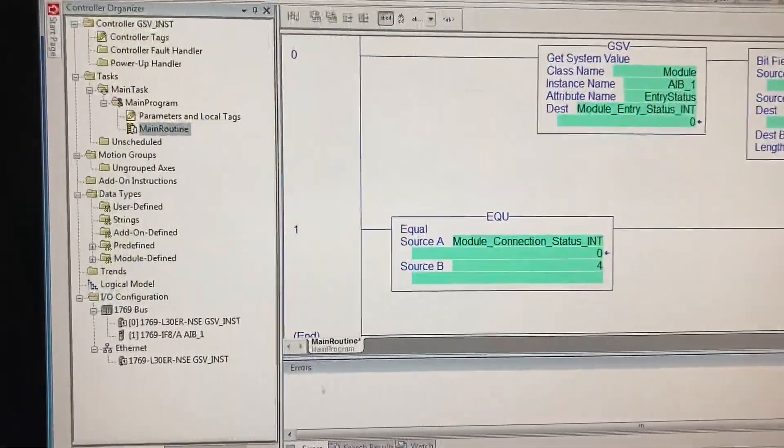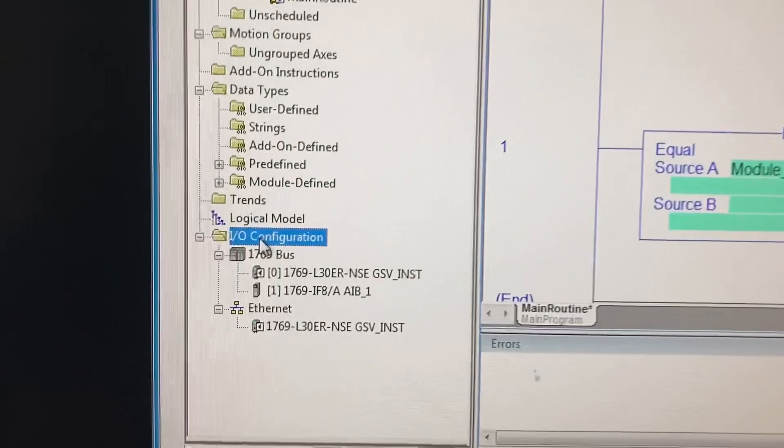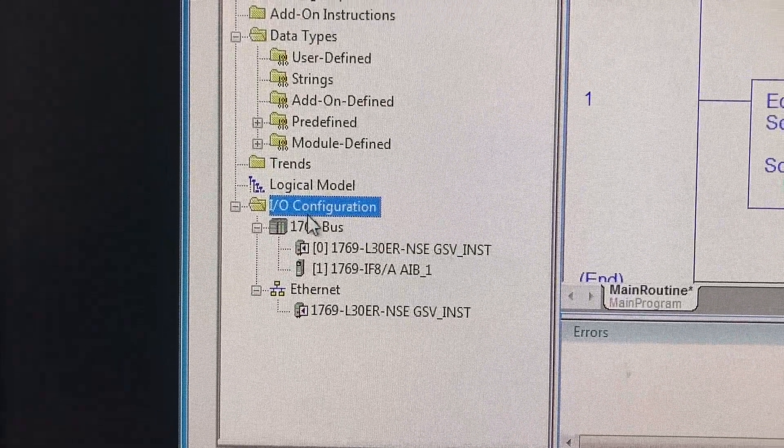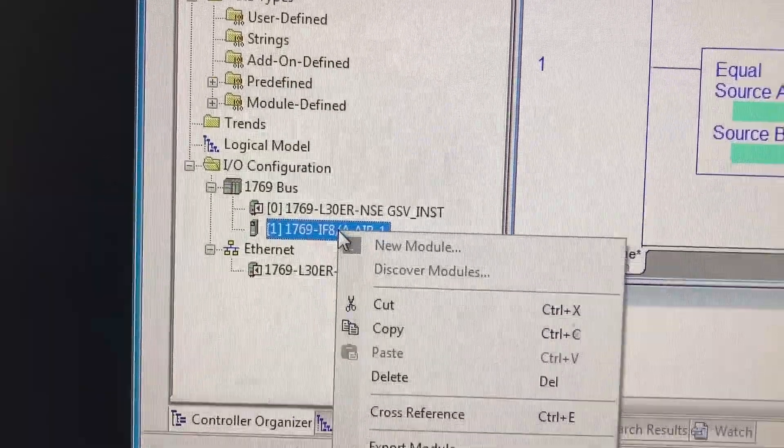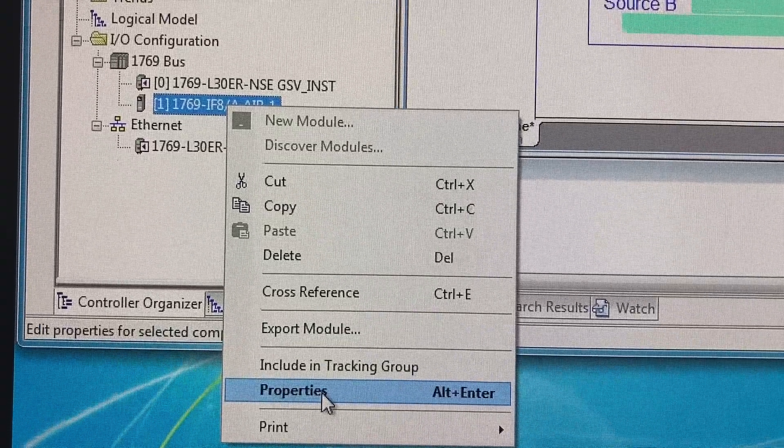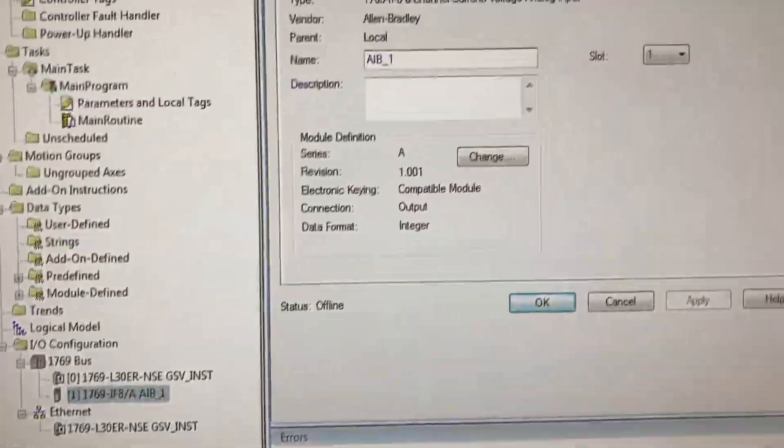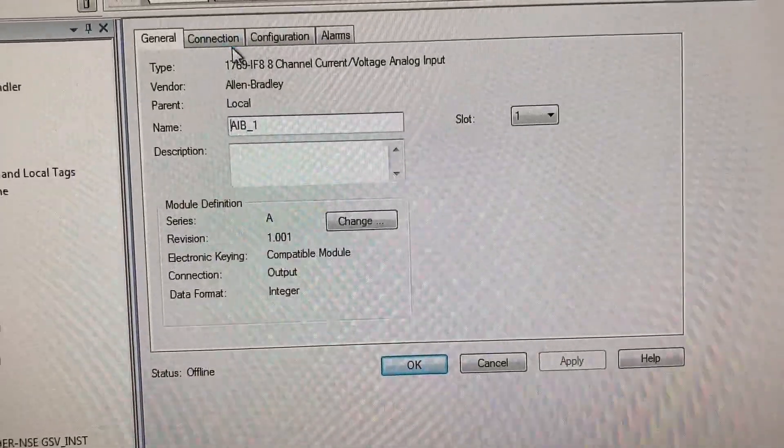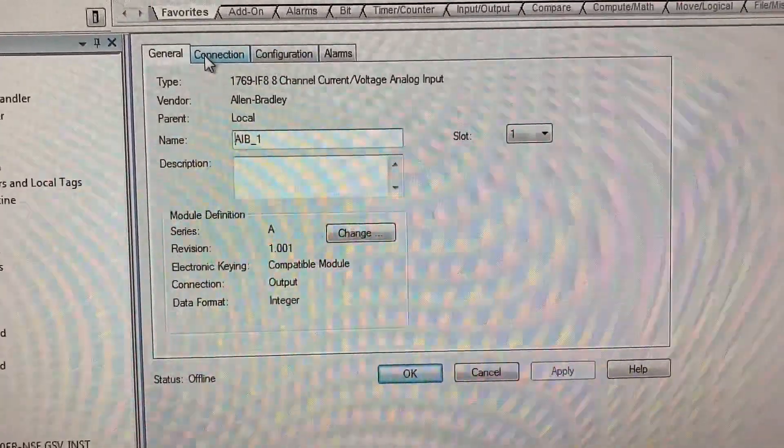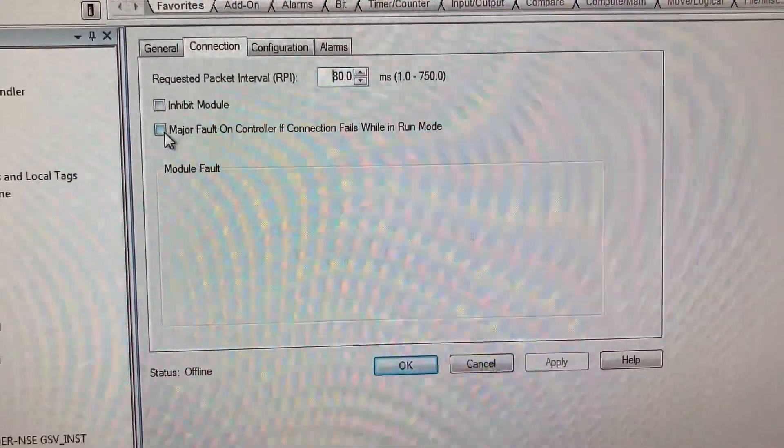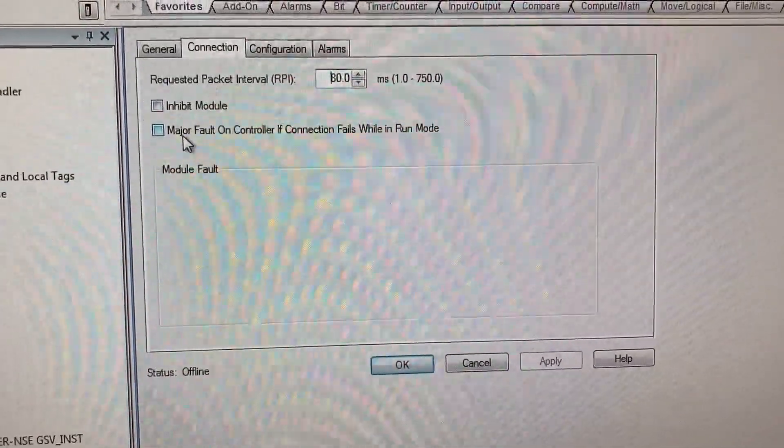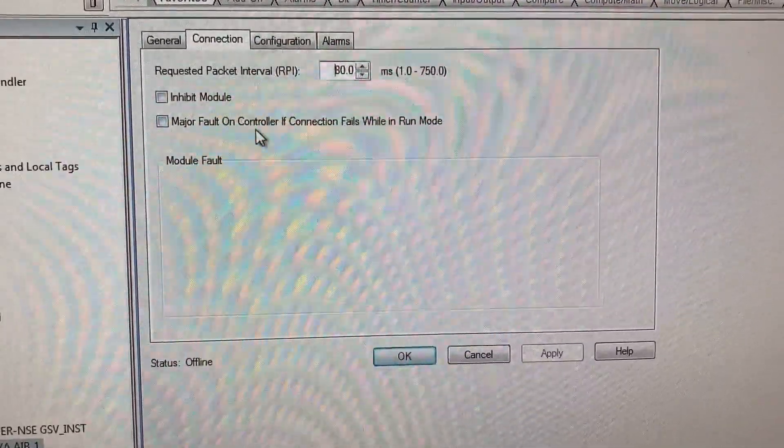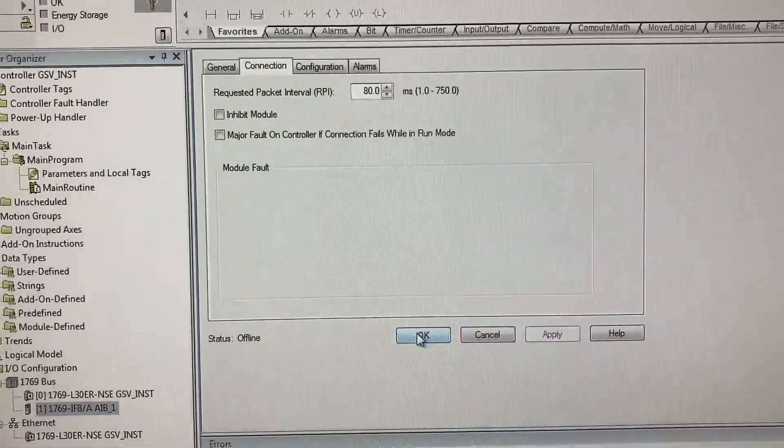Last thing before we download it to PLC, go to IO configuration, right-click on the module, go to properties, go to connection. Make sure this box is unchecked to prevent major fault on controller if it doesn't see the module.